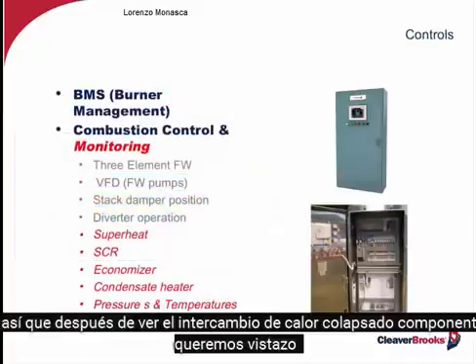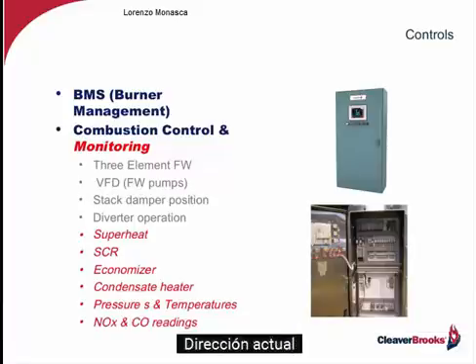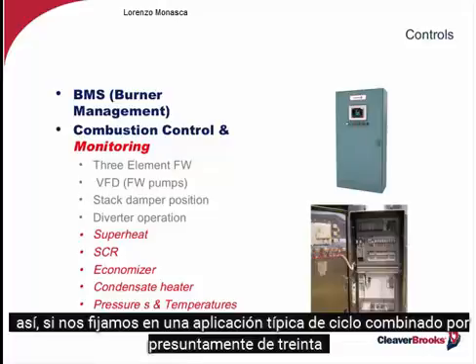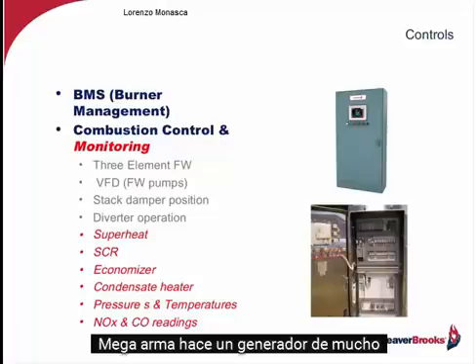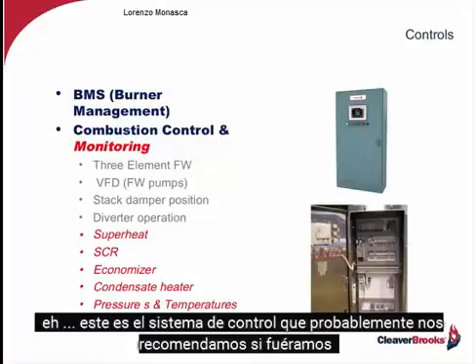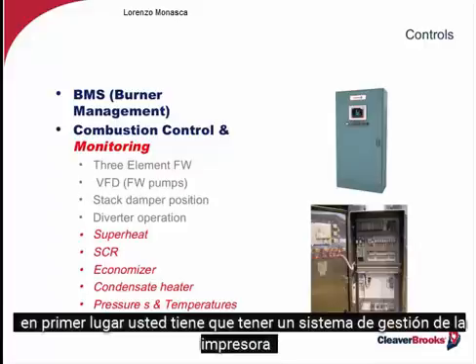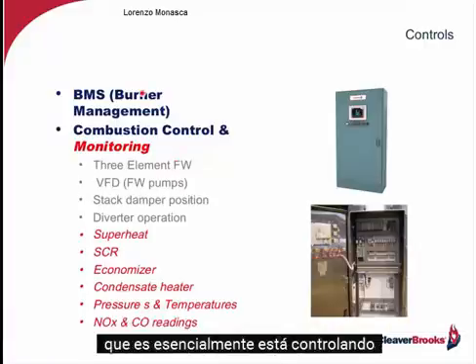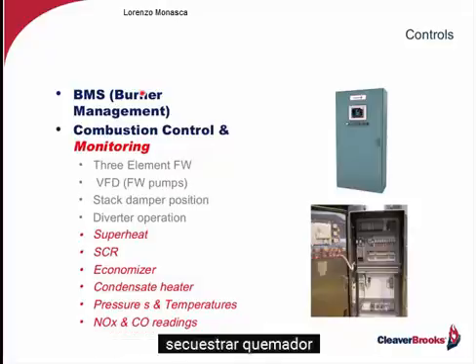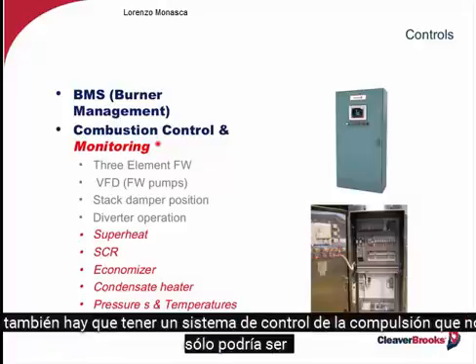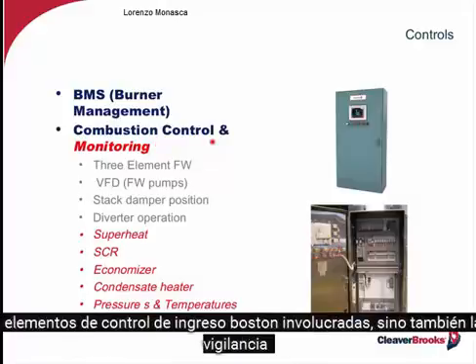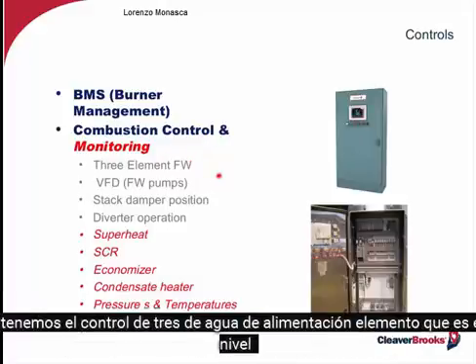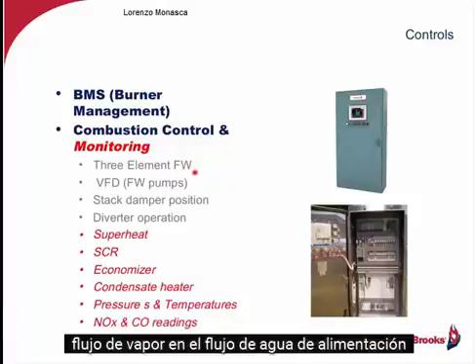So after looking at the heat exchange, the last component we want to address today is how do we control all of this? Well, if we look at a typical combined cycle application for, let's say, a 30 megawatt generator with supplementary firing, this is the control system that we would probably recommend if we were doing it. First of all, you have to have a burner management system, which essentially is controlling the duct burner, just like it would in a standard fuel-fired boiler. We also have to have a combustion control system that's not only going to be involved in combustion control elements, but also monitoring. So in this particular case, for this job, we've got 3-element feed water control, which is level, steam flow, and feed water flow.